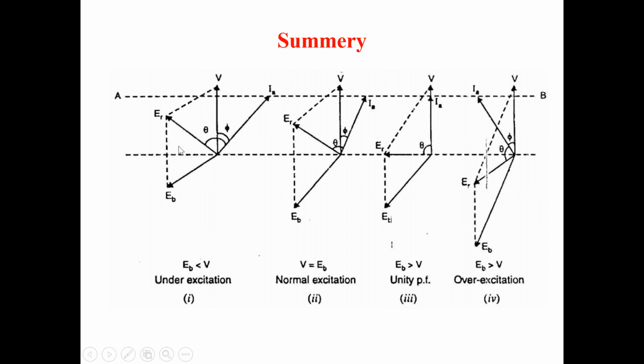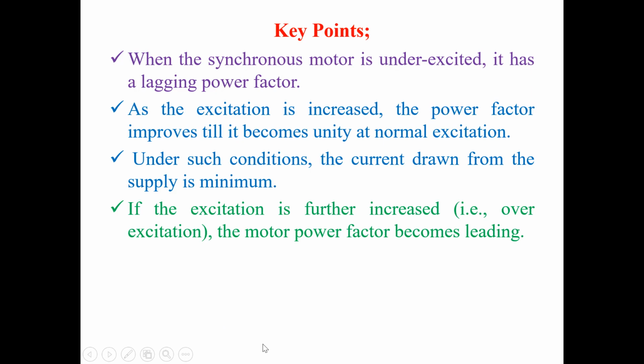Beyond that it becomes leading. So from maximum lagging to leading, it changes as we change the excitation. This case, where the motor draws current at leading power factor, is known as overexcitation. When Eb is slightly greater and input voltage and current are in phase, that is unity power factor. When both are the same, that is normal excitation, and if Eb is lesser, it is under-excitation.